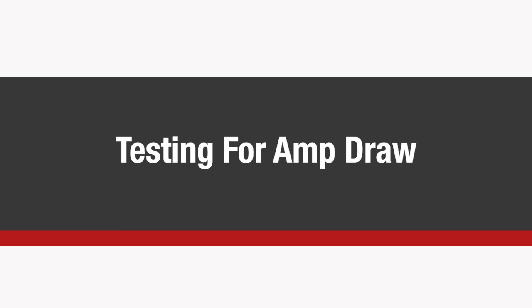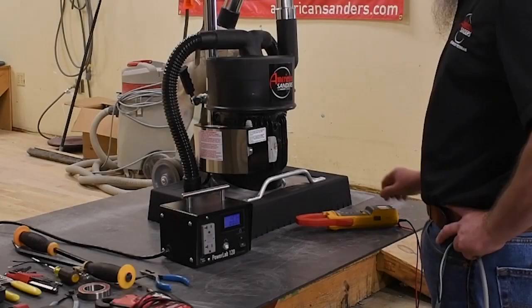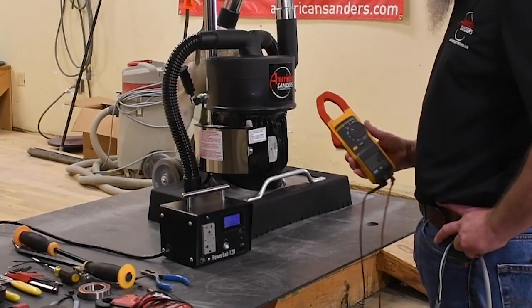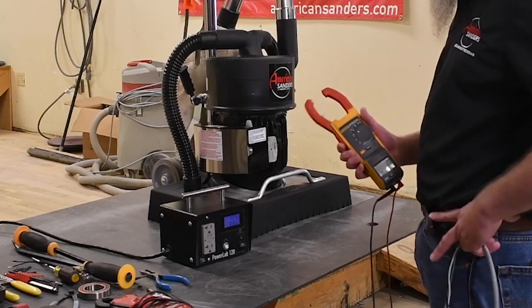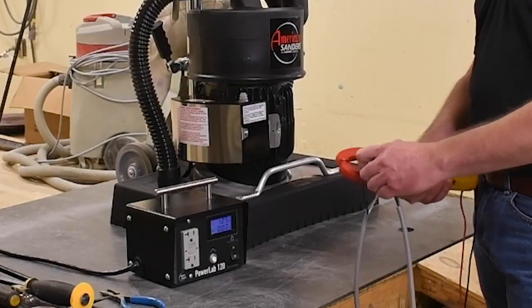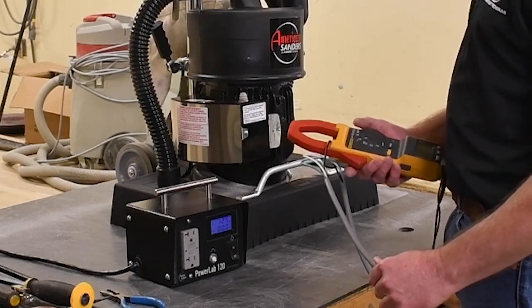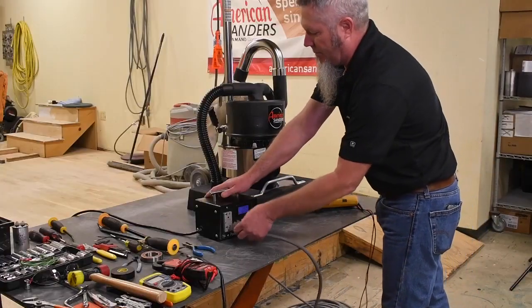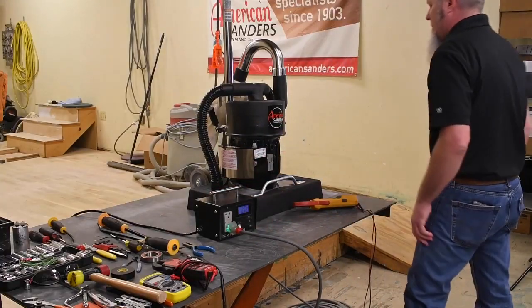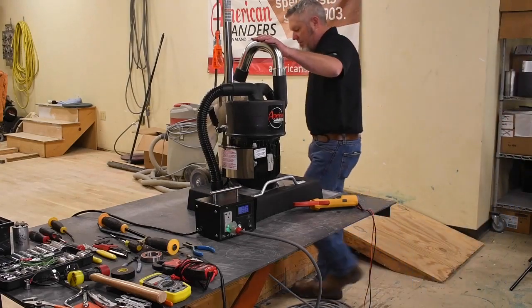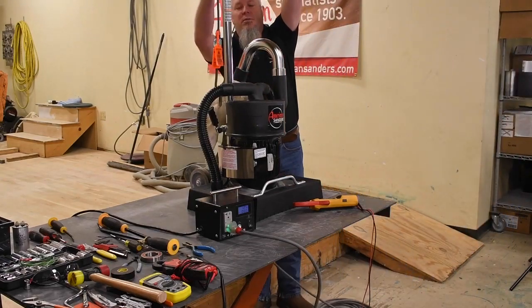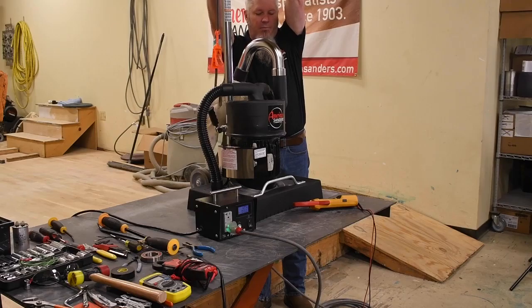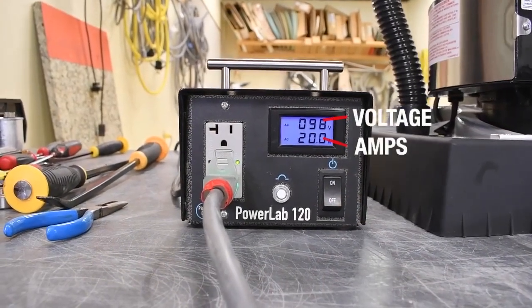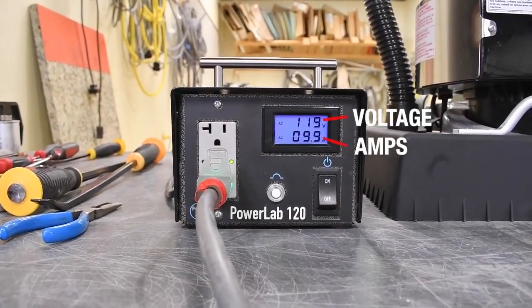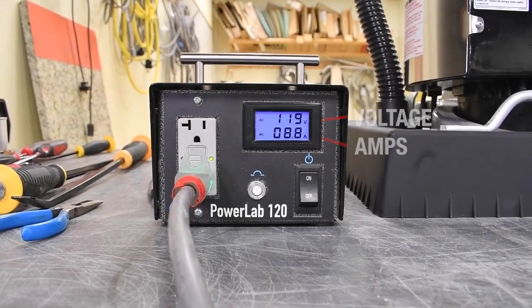How to measure amperage draw. Measurement of amperage draw is traditionally done with a clamp-on ammeter. A modified adapter cord is required for this process to access the individual wires in the circuit. To use the PowerLab 120, simply plug the machine or tool you want to test into the unit. Then turn the machine on to immediately see the amperage draw and voltage drop of the machine. This is the first step in troubleshooting operational problems with the machine.